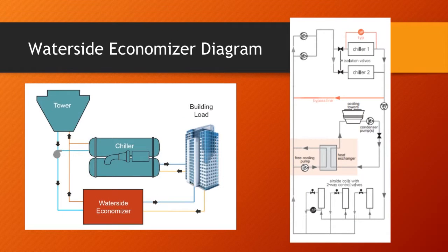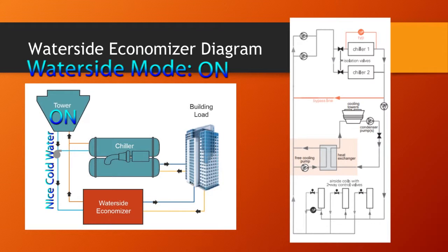So here we got two diagrams of water side economizers. This one's a bit more simplified than that one, but this in essence is how a water side economizer works. It's basically kind of another chiller, but it doesn't have a compressor on it. So you would have, in addition to your chiller piping on your condenser water loop, you'd run another set to a big heat exchanger. So when you're ready to use water side economizer mode, you turn your cooling tower on, send that nice cold water from the tower through the water side economizer heat exchanger, and then that's going to pull heat from your chilled water loop, transfer it to that water, and then take it outside.